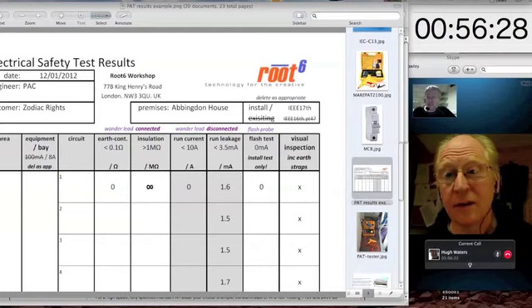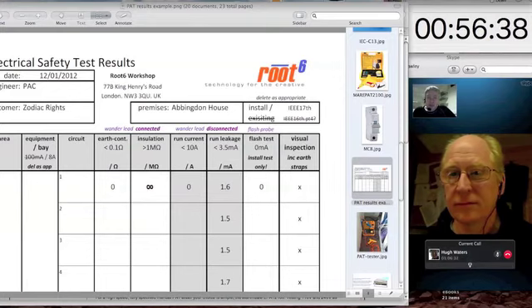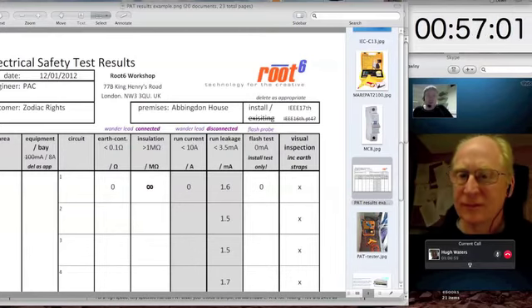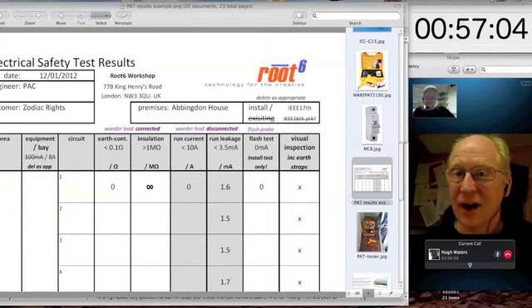And so you've got to say to yourself, they use their own brand of PDUs on all the builds they do, and you see them all over Soho and all over broadcast, and so presumably they're not actually testing these, because they'd have to hand over test sheets that said, actually, we failed on all our earth leakage measurements, all our run leakage measurements, and we can't do any better than just the PDU by itself. As soon as you start hanging cables off it, there are tiny amounts of earth leakage down cables and things like that. But their actual PDU has more than 4 milliamps, i.e. more than the allowable amount for the whole system within the PDU. And so that's why I quite like the way Bryant Broadcast manufacture their PDUs, because they're all done nicely, and you never come up against this shenanigans. And they're a lot more expensive as a result.